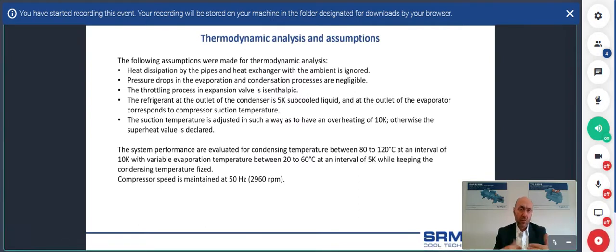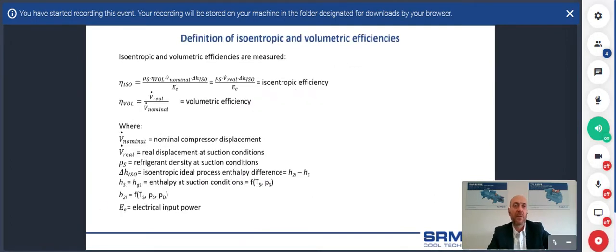So we do the testing with a procedure that fixes the condensing temperature at a value between 80 and 110 degrees, changing it in steps of 10K. And during the fixed condensing conditions, we then change the evaporating temperature in steps of 5K between 20 and 60 degrees C. The compressor for the normal testing is maintained at fixed speed, so at 50 Hertz, but it can also be used with inverter with different frequencies.